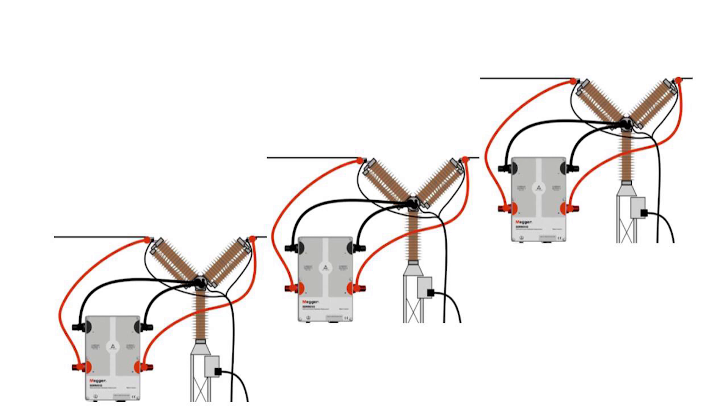Here is an example where we have connected one box on each phase on all three phases. The breaker has two breakpoints. And we measure this three phase breaker all breakpoints at the same time. Six breakpoints in total.